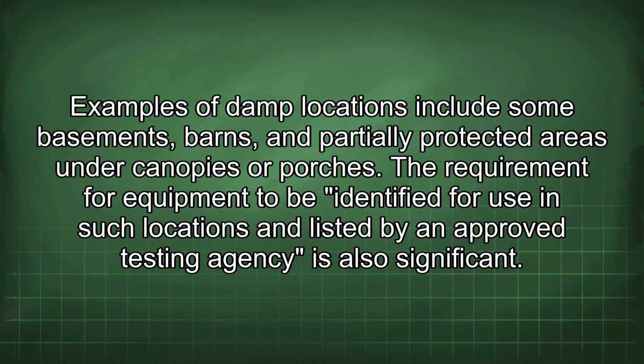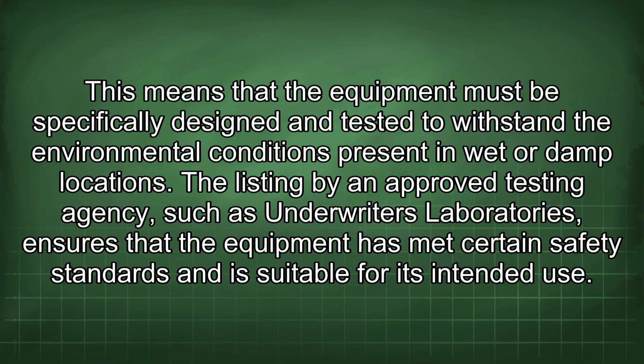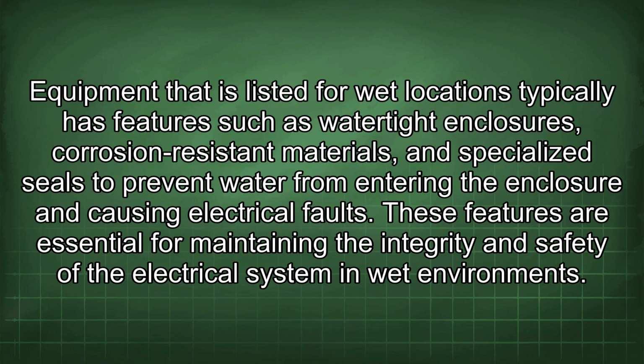The requirement for equipment to be identified for use in such locations and listed by an approved testing agency is also significant. This means that the equipment must be specifically designed and tested to withstand the environmental conditions present in wet or damp locations. The listing by an approved testing agency, such as Underwriters Laboratories, ensures that the equipment has met certain safety standards and is suitable for its intended use. Equipment that is listed for wet locations typically has features such as watertight enclosures, corrosion-resistant materials, and specialized seals to prevent water from entering the enclosure and causing electrical faults. These features are essential for maintaining the integrity and safety of the electrical system in wet environments.